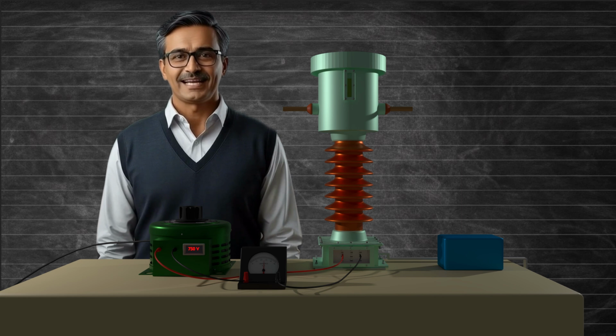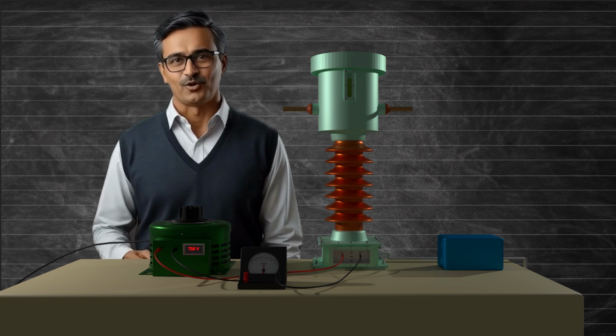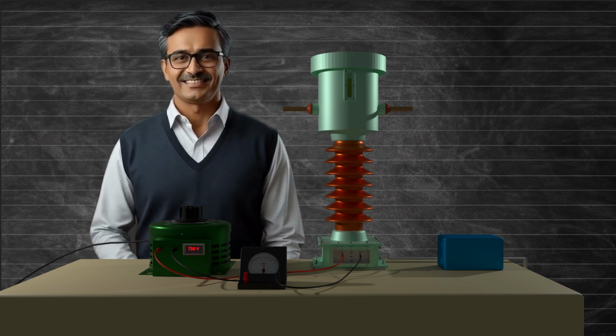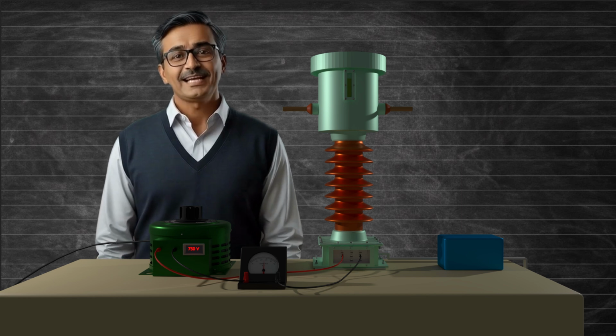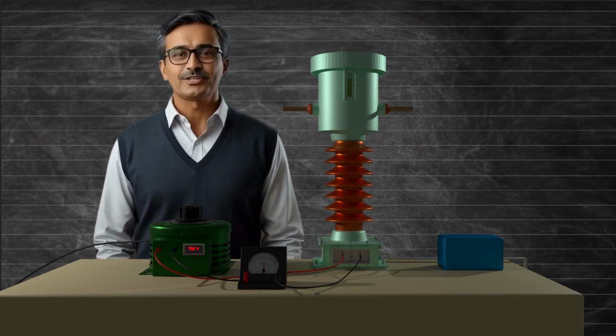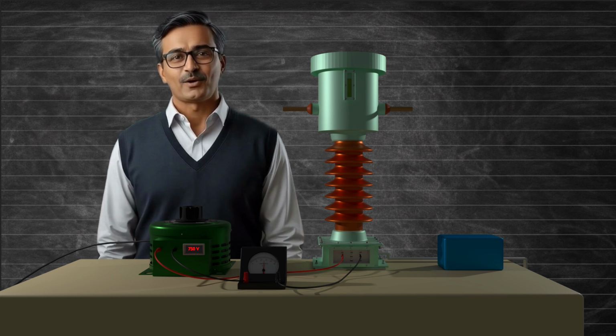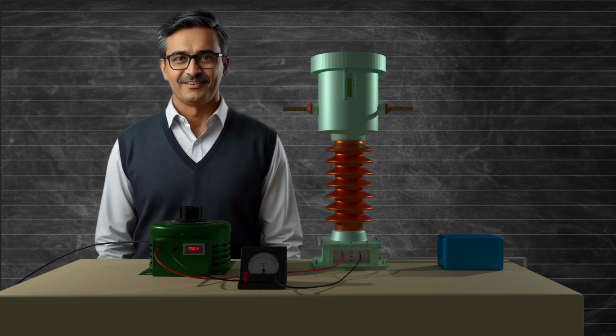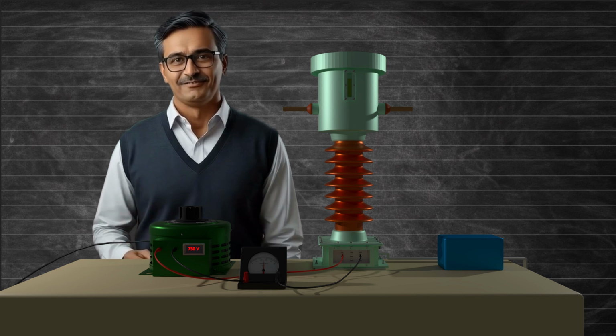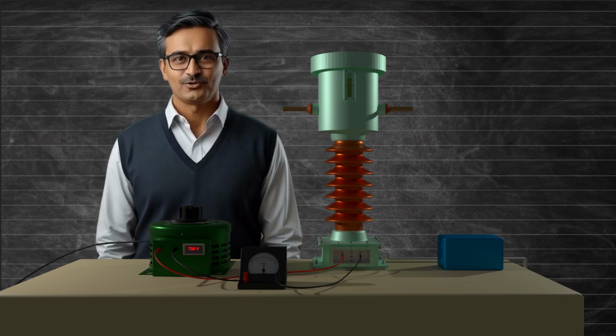This is something very important to remember. The 4.5 kV mentioned as the limiting value of the secondary winding during the inter-turn overvoltage withstand test is actually the peak value of the voltage, not the RMS value, as specified in IS 2705 Part 1, 1992.